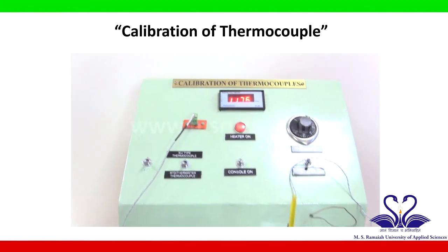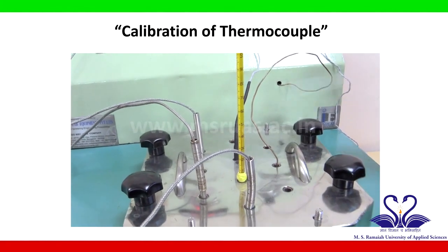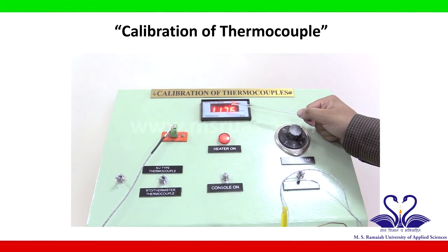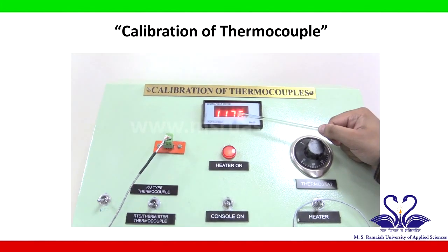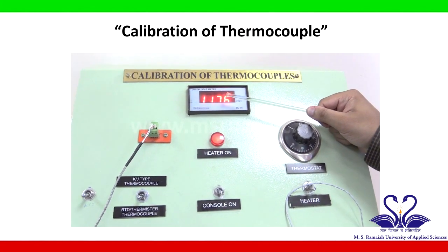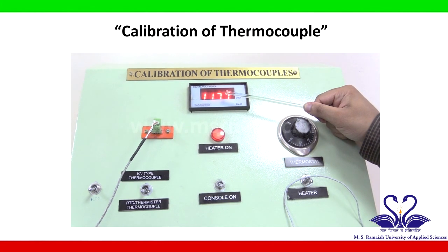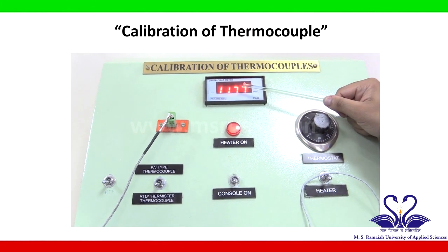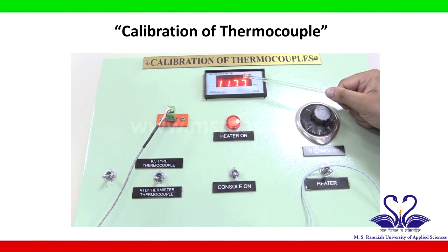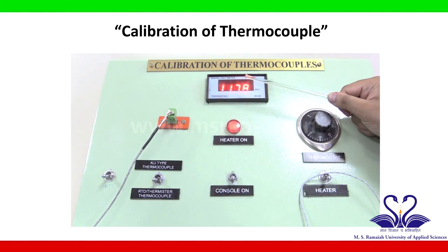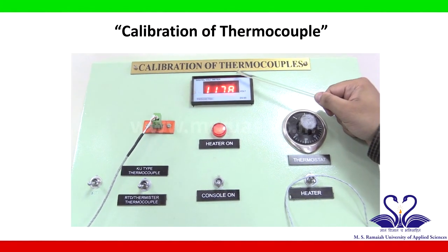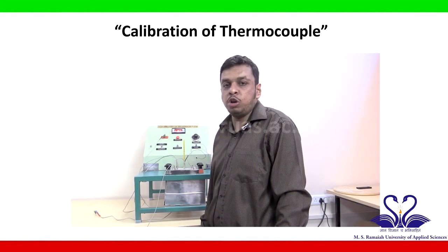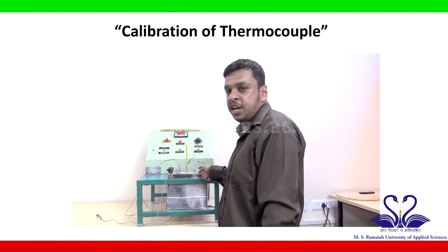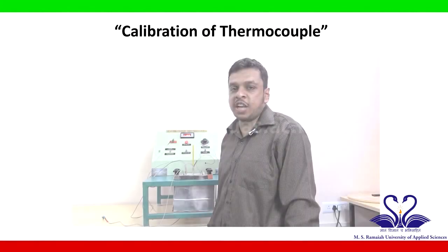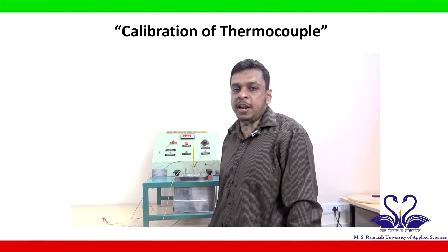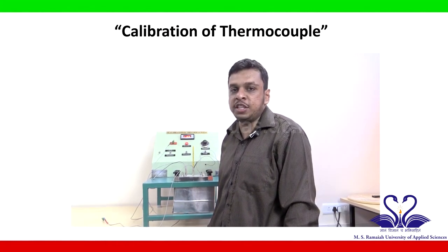Now note down the values for the corresponding temperature and the digital reading. It is important to note that when you have connected either an RTD or a thermistor, the digital display reading changes to resistance being measured instead of voltage. The resistance being displayed in the digital display is in form of ohms. For an RTD, always multiply the value being shown in the digital display by 10. Similarly, note down 4 to 5 different combinations of temperature and resistance. Now, using the standard formula for RTD, calculate the theoretical possible values of temperature and resistance combinations.